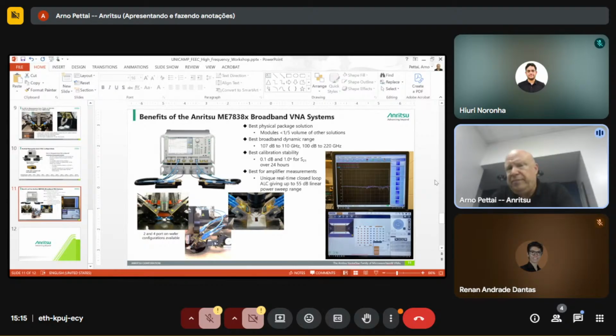But really the most amazing part of this system is the calibration stability, how it's able to keep a calibration over a long period of time. Of course, the assumption is that the environment of the room that the system is in is also held fairly constant. But we're able to perform to 1/10 of a dB on transmission measurements or a degree phase over a 24-hour period, which is truly phenomenal, which means we don't have to worry about calibrating as often and have more confidence in the measurements that we're making.